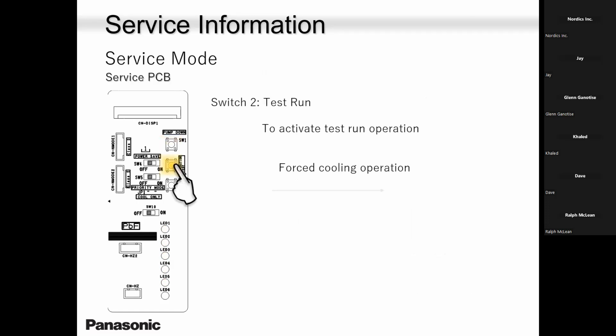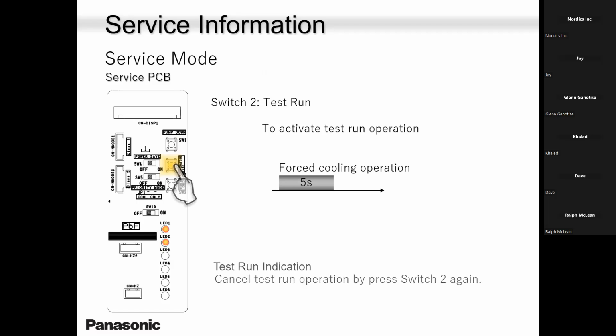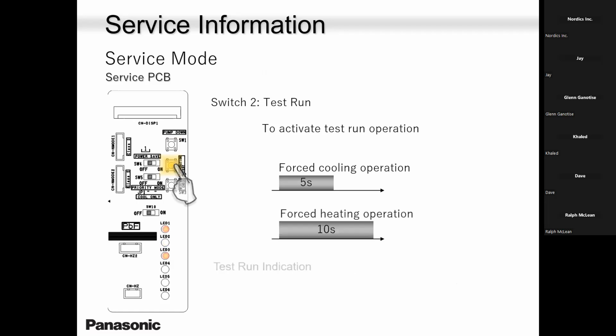Test run, guys, for forced cooling, it's the LED 1 and LED 2 will come on. You are in test run cooling. And if you don't want test run cooling, you want test run heating, you have to keep pressing, and the second light will go off and the third light will come on. Okay, so let me show you test run heating. Press and hold until the second light goes off, and then the 1 and 3 comes on. You're in test run heating. At that moment, you can hook up your gauges before you perform, so that you can see your gauge pressure. You can hook up your running amp meter and stuff like that.